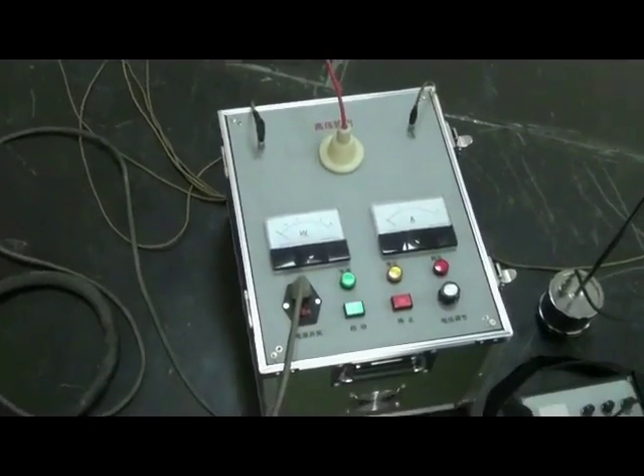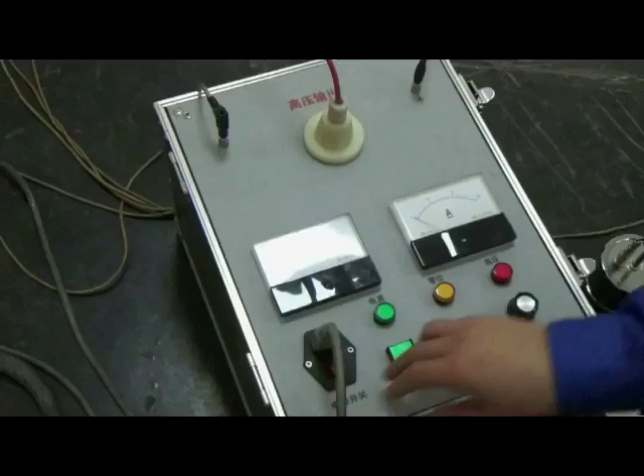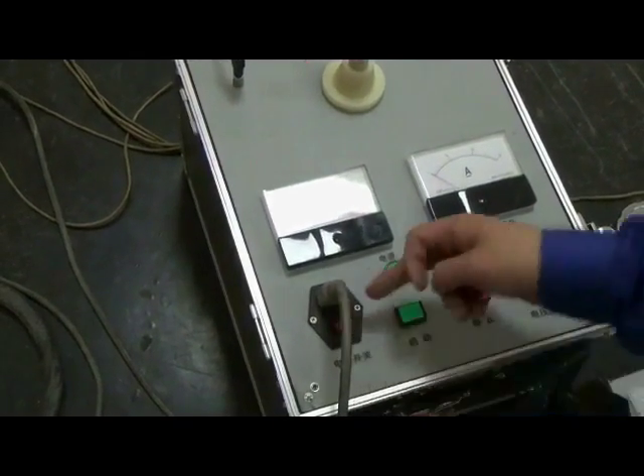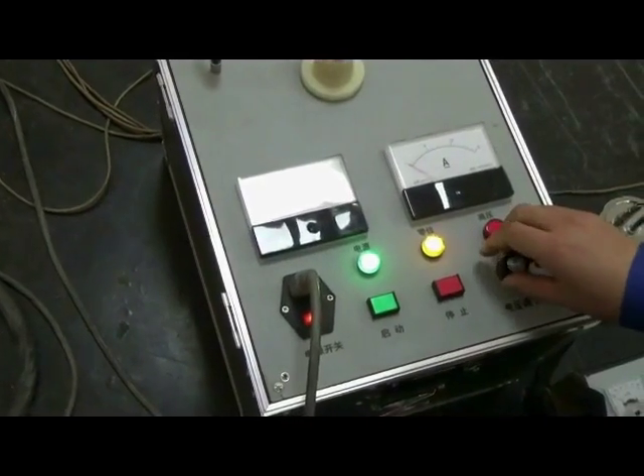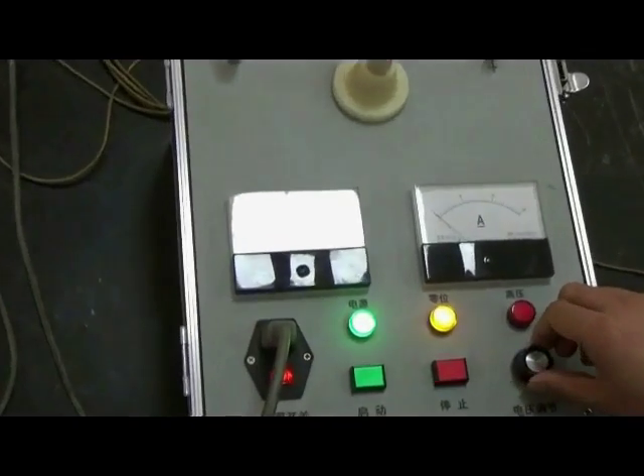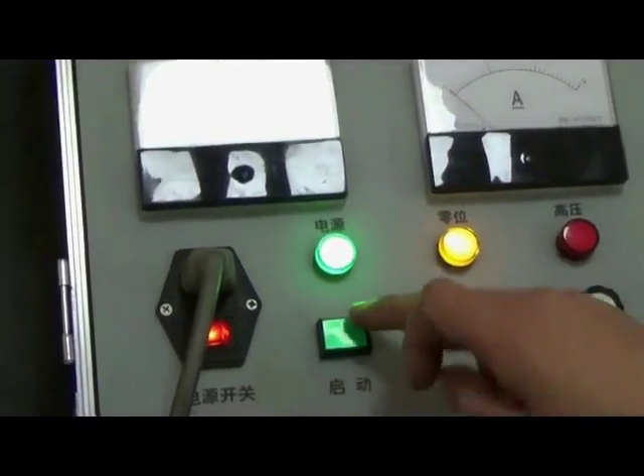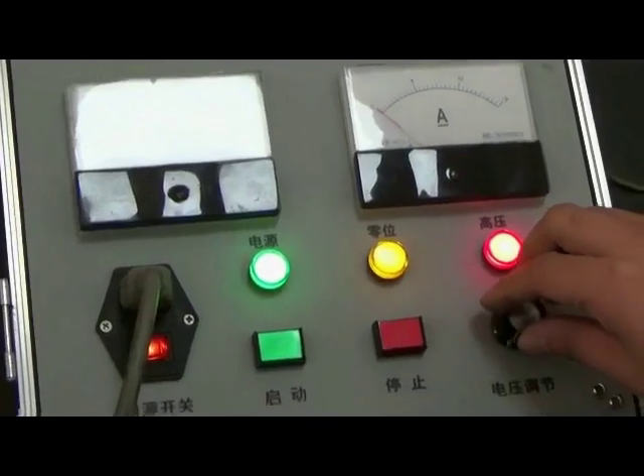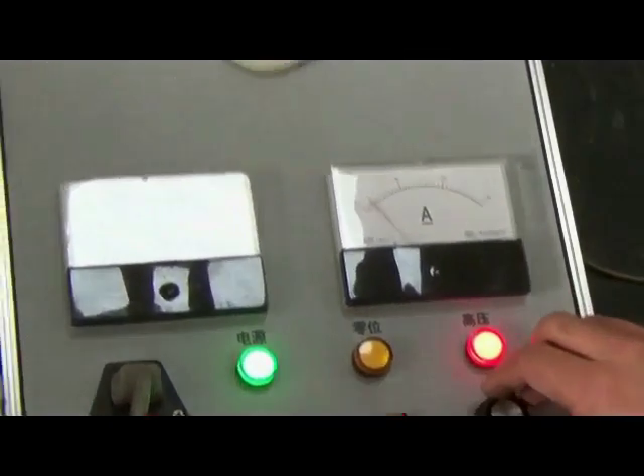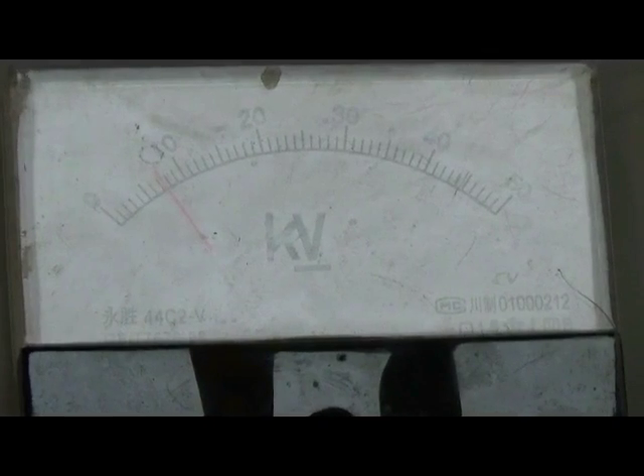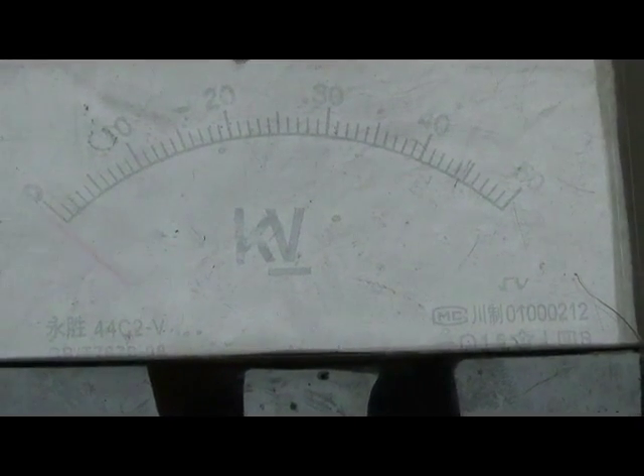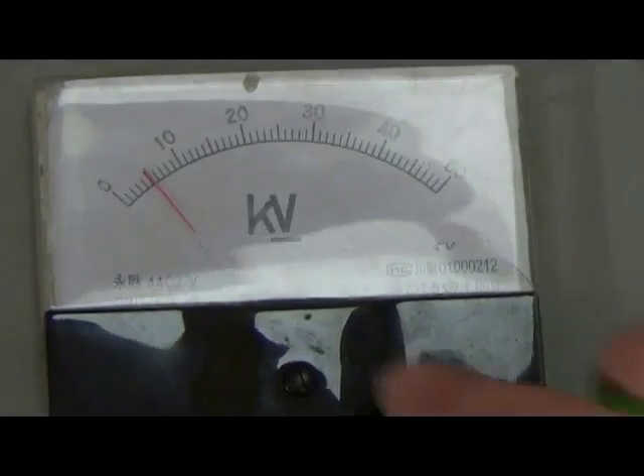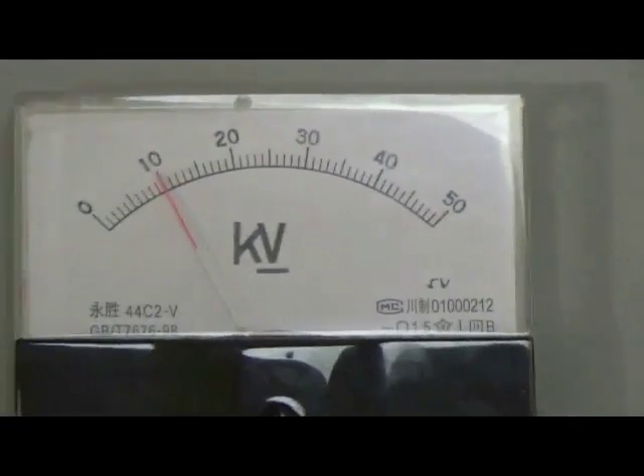Now we operate power supply. The method is DC flash over. Turn on switch. Adjust voltage to zero. Starting up, high voltage light on. Clockwise adjust voltage. Notice indicator. Here swing rate is large, that means the fault point has already been discharged.